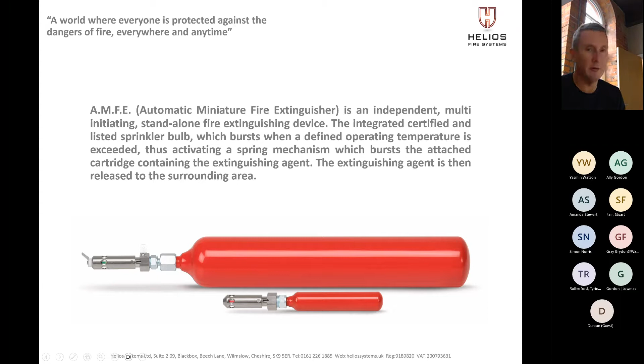We can see here, this is the nozzle. Inside this nozzle here, we have a sprinkler bulb, and these are set either 68 degrees or 93 degrees, or in the case of where we're using our AMFE, it has a metal coating painted onto it, and these contactors here and here are connected to a relay-based smoke detector. That relay-based smoke detector, upon it detecting smoke in the area, sends a 9-volt signal through the contactors, which then goes across the bulb, shatters the bulb, and then discharges the system. Again, you'll see that as we go through the presentation.